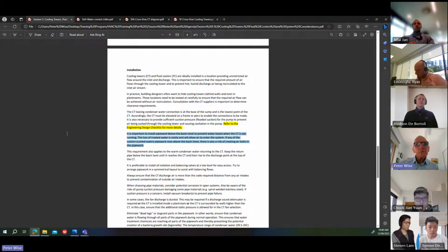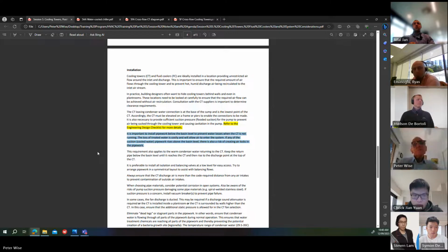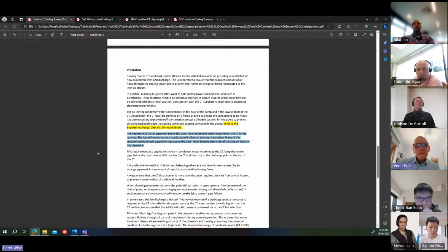So it's important to install pipework below the basin level to prevent water losses when the cooling tower is not running. So you've got an open basin in a cooling tower. When the system turns off, you've got a head of water in the basin which can leak through the condenser water system.